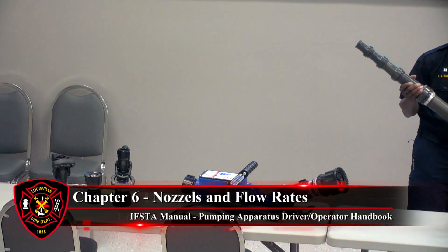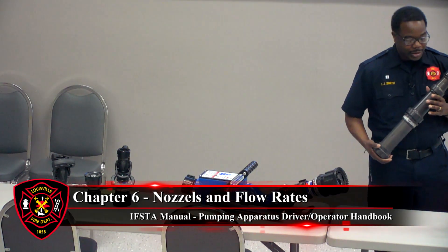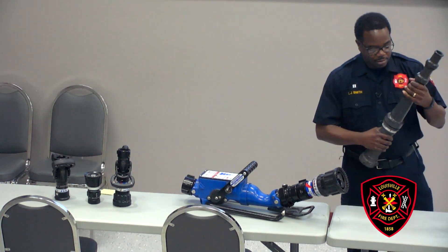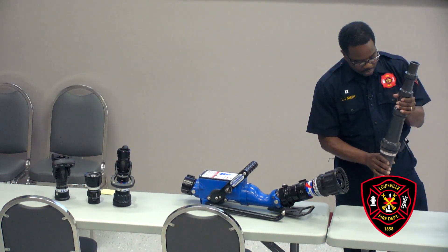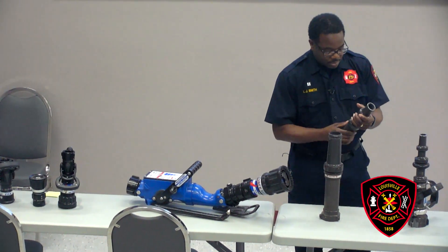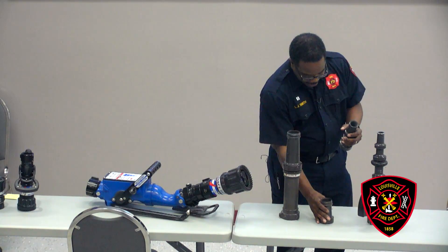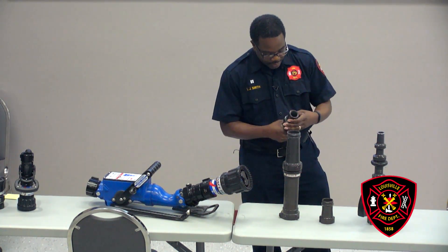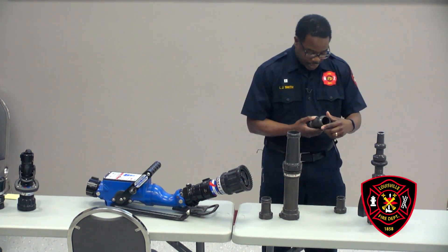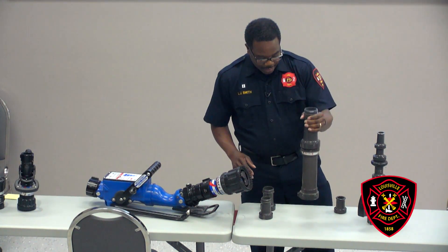Our smooth bore tips can be put on our monitor — either mounted or removed for portable use. We have four tip sizes: inch and three-eighths, inch and a half, inch and three-quarters, and two inch, flowing approximately 500, 600, 800, and 1,000 gallons per minute respectively.